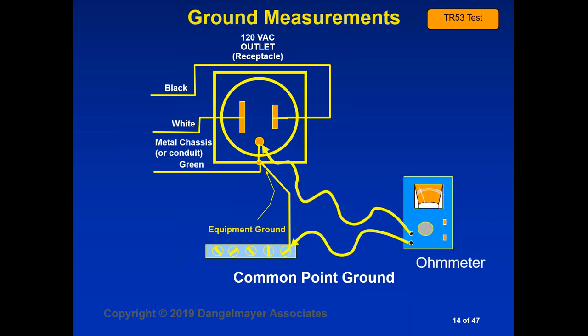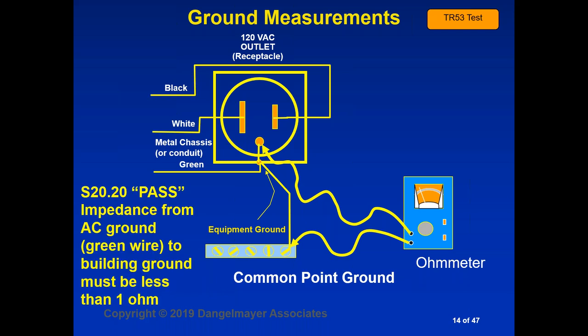So if we didn't have a particular meter, one of the things we need to do is to check the resistance between the common point ground and the metal chassis ground to make sure we have a good ground connection there. We've already verified our green wire ground impedance, and now we need to measure the resistance between the common point ground and the chassis ground, and that should also be in the 1 ohm range, as you see there.